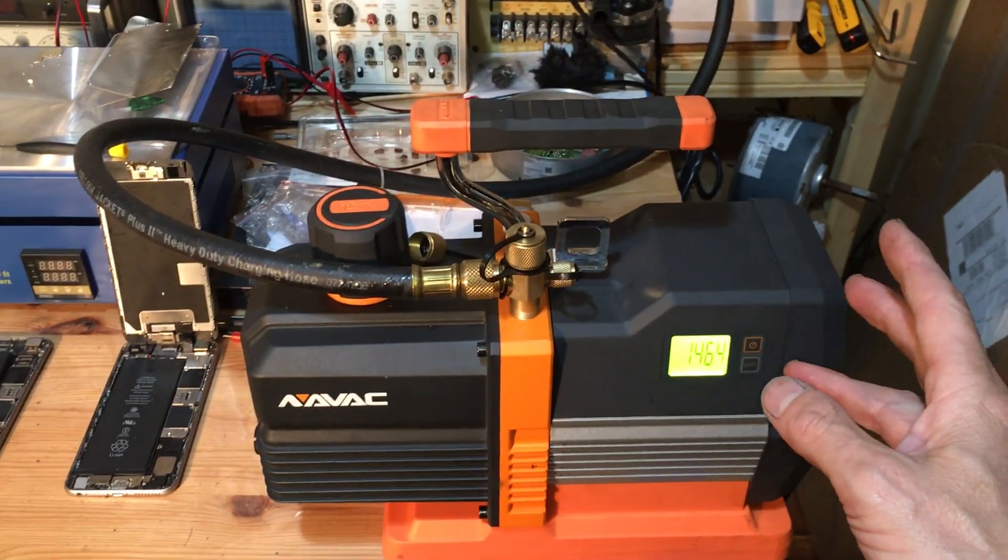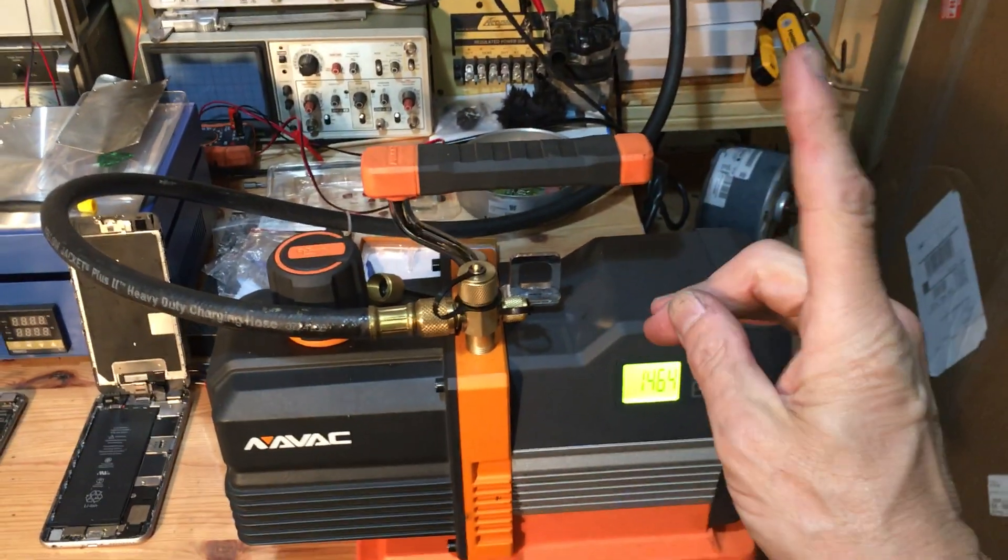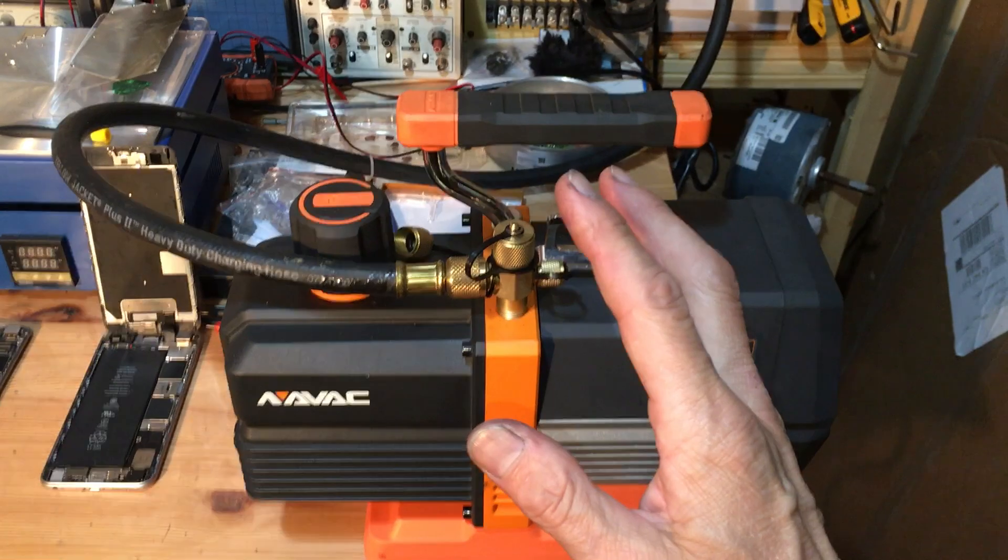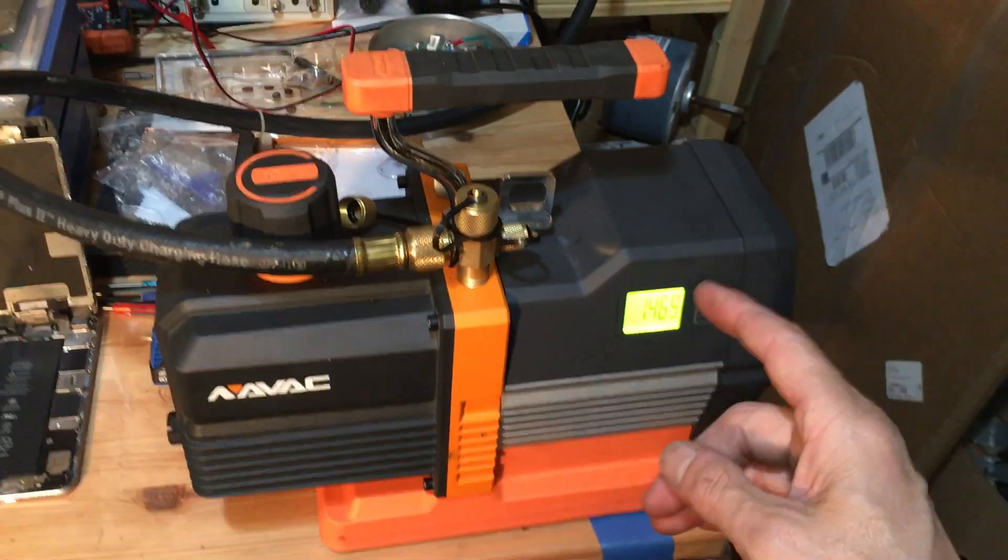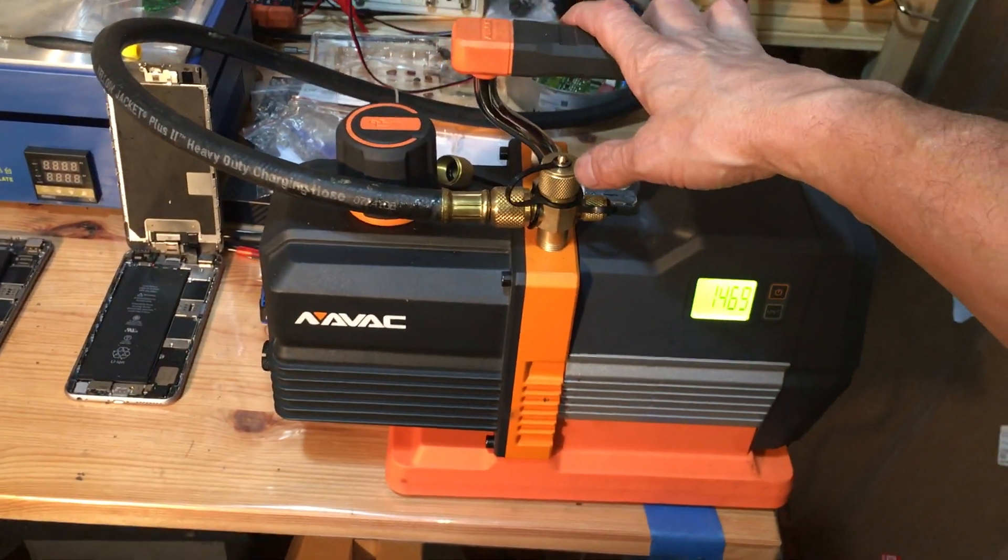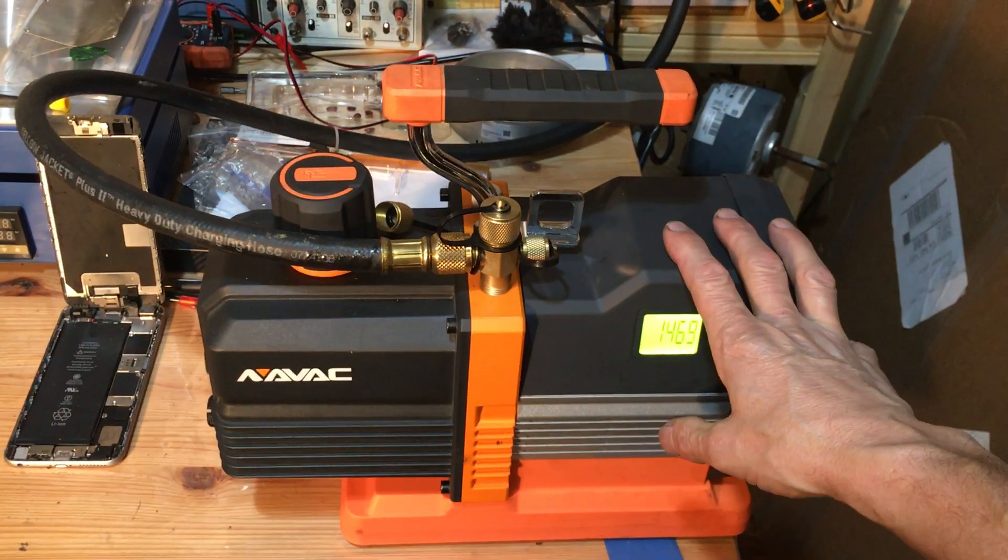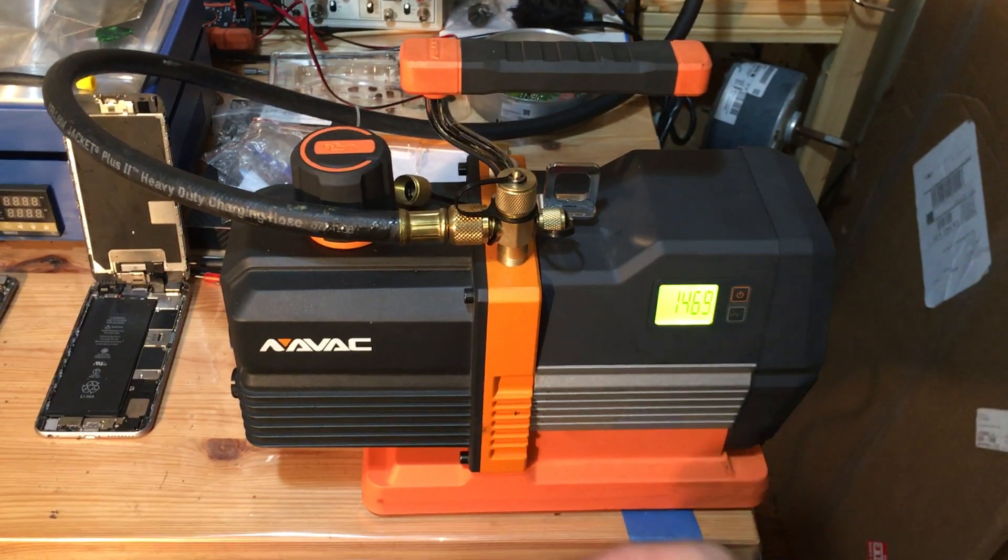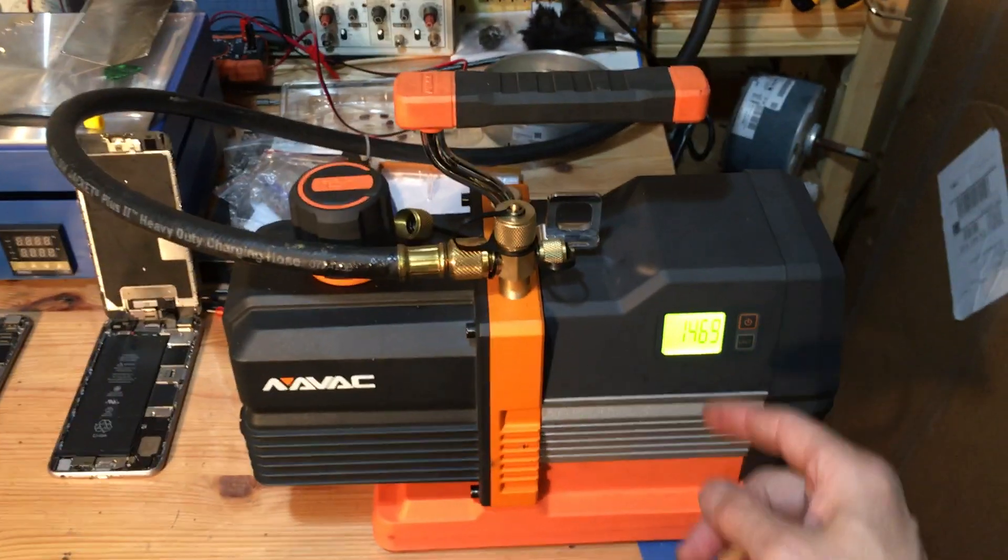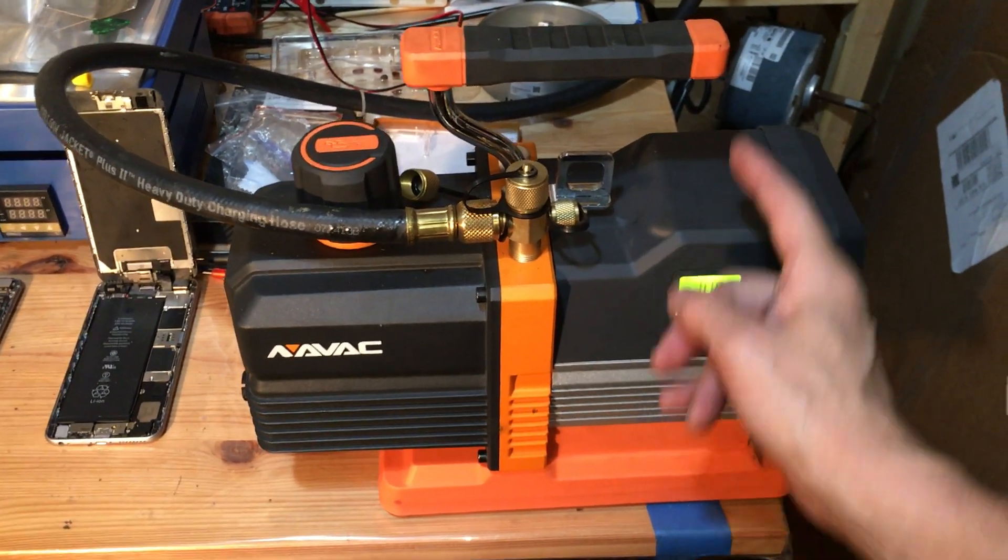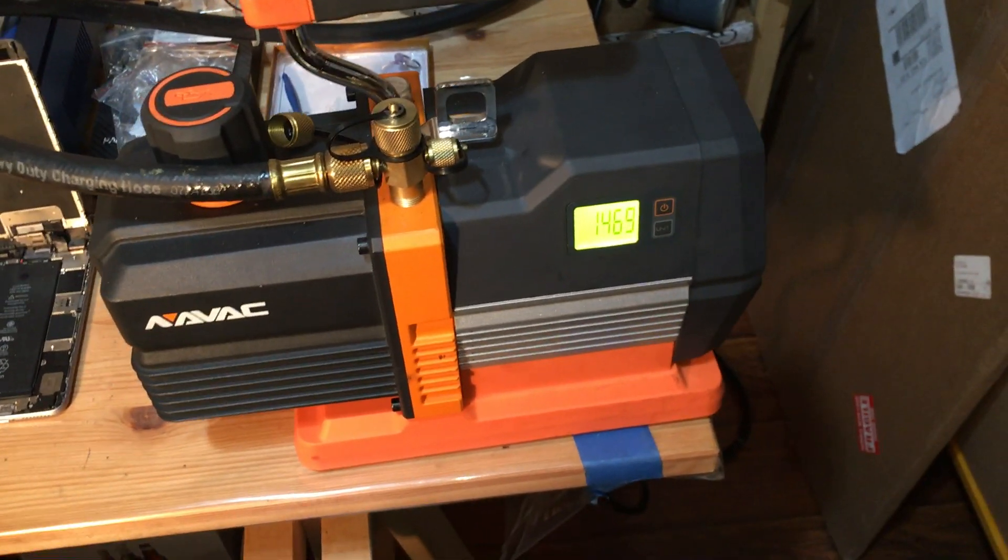That's a great visual and audio feature to let you know, because reaching 500 microns means absolutely nothing. As soon as you reach 500 microns, that is just when you started to do work. Nothing's really being achieved too much before that. It'd be nice if they had a second setting where you could go down to like 200 microns or below for a half hour and then shut off. But 500 will have to be good enough. It lets you know that you can keep this pump on. It could take you one hour, 30 minutes, or 10 hours before you reach 500 microns. But no work was really done until you hit that 500 microns and then kept on pulling after that.